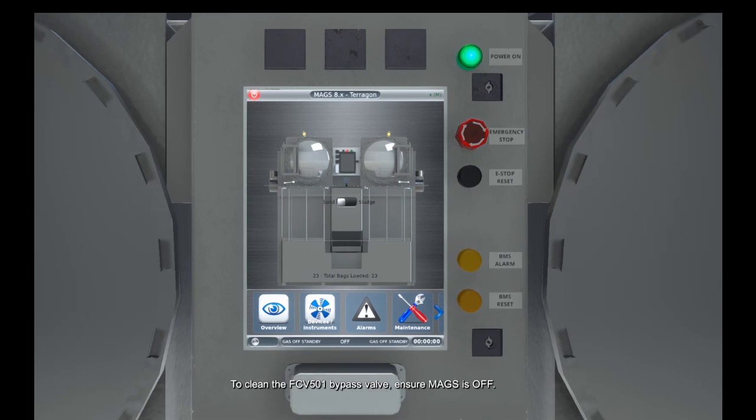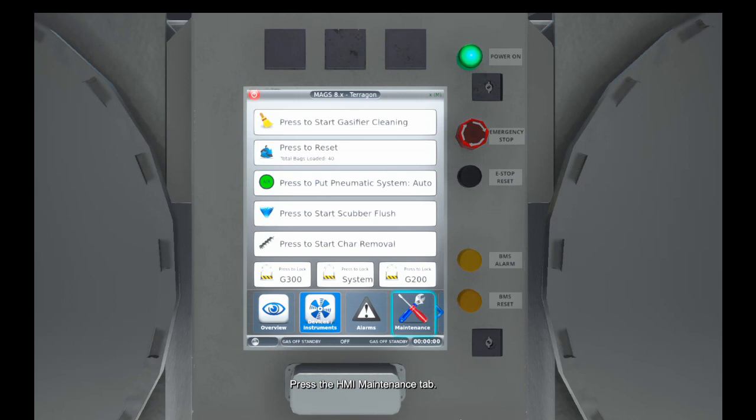To clean the FCV501 bypass valve, ensure MAGS is off. Press the HMI Maintenance tab. If the pneumatic system is on, select Press to put Pneumatic System Auto to turn the pneumatic system off.